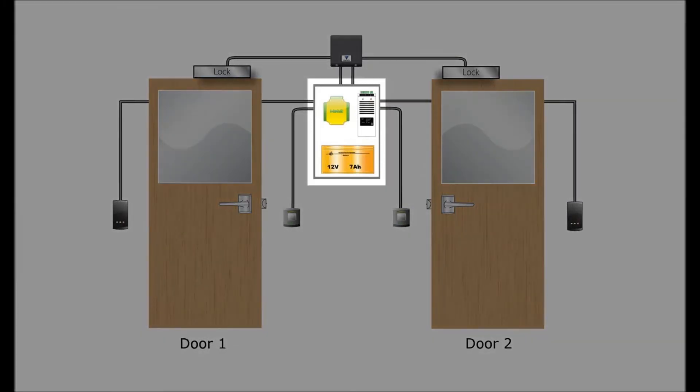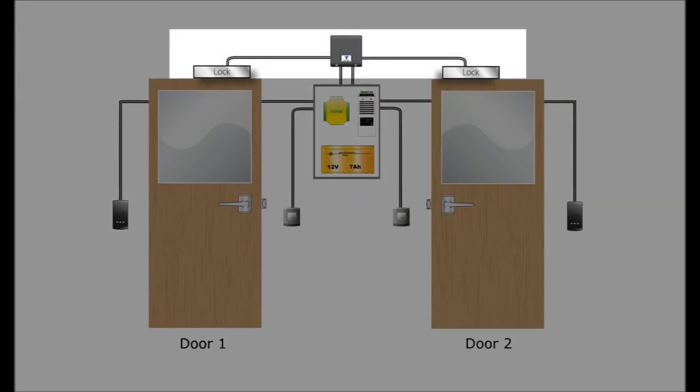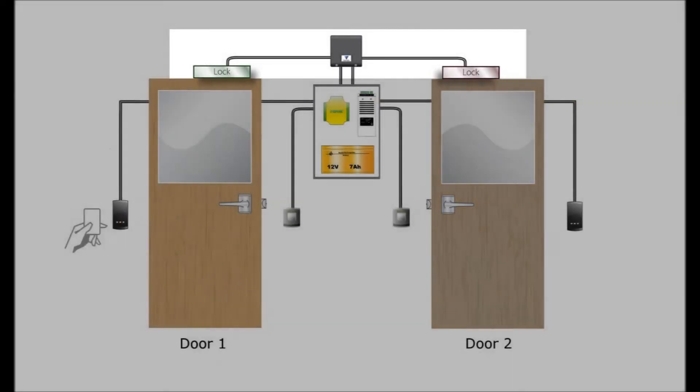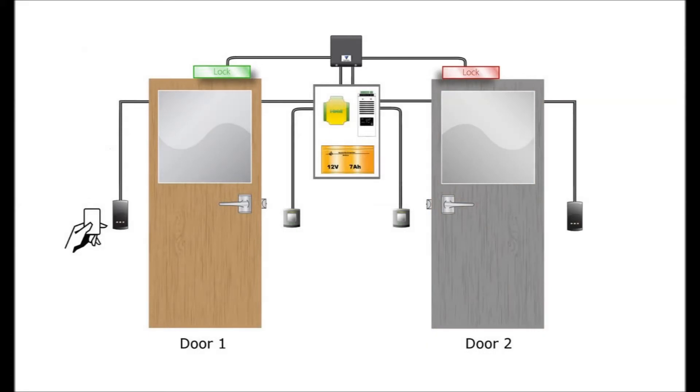Net 2 will determine the access when a token is presented, but the interlock will only open the relay provided the two doors are in the correct state. So, provided door 2 is closed, when a token is presented to door 1, door 1 will unlock and can be opened.